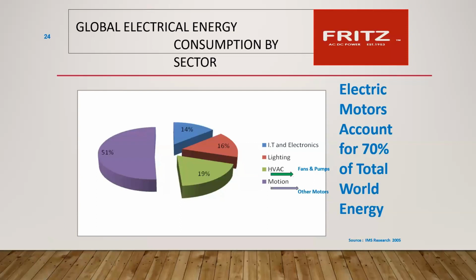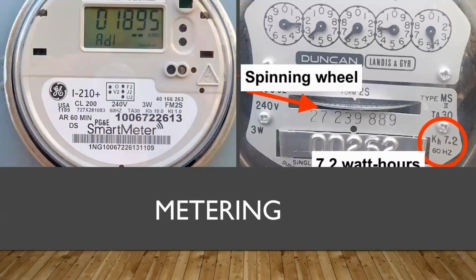So again, motor consumption in the world is a very big factor, and there's a lot done out there pushing solar and wind. But my feeling is if we attack motor utilization, 70% of our world's power, and reduce that, we don't have to do as much generation. HVAC and industry motion is about 51%, lighting is about 16%, and about 14% is electronics. So the real key is to slow these darn meters down. And you do that by putting a control in between the motor and the drive.